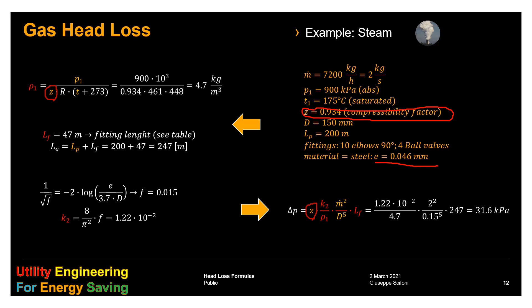And by plugging the values inside, we come to the delta P, in this case 31.6 kilopascal. We present here a table, resuming table, with all the formulas seen up to now. The first 2 rows are referring to the liquids. For water and oil, the pressure loss is expressed in meters, and the coefficient K and K1 are represented also here for the simple case where the material of the pipe is steel. For the oil, we remember K is a pure constant.